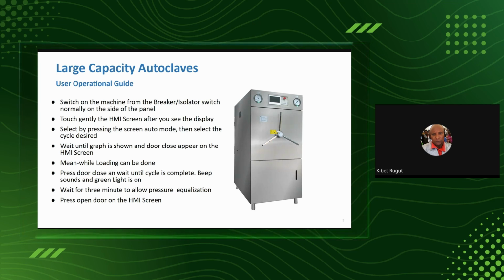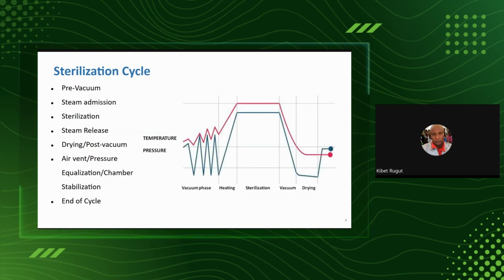So as per the operator's guide, which varies across the models, you are allowed maybe to wait 3 or so or 5 minutes before you open the door. Here you strictly follow the instructions in the operating manual. So a sterilization cycle is going to be beyond the cycles that we have in the small tabletop.